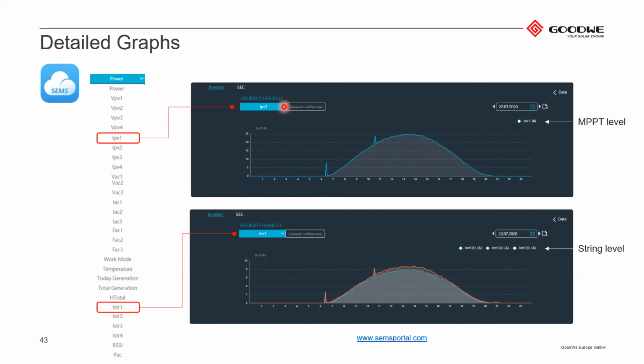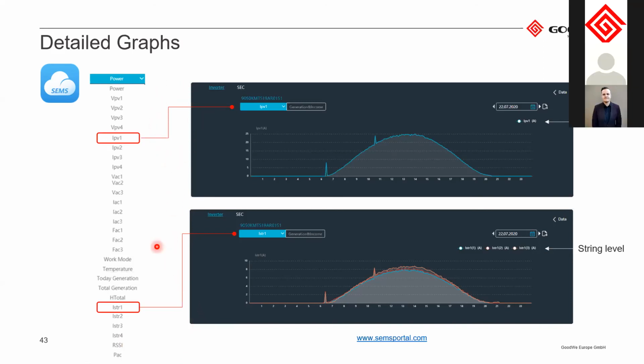Basically, here's the drop down menu, and you can select a lot of different things. You can select the current per phase, per string, per MPPT. Same with the voltage. You have the power. You have the temperature. You even have the Wi-Fi strength here, the RSSI. So in case the customer is calling and saying that the inverter is not connected anymore, it could be due to faulty Wi-Fi, and then you can check the Wi-Fi strength here.